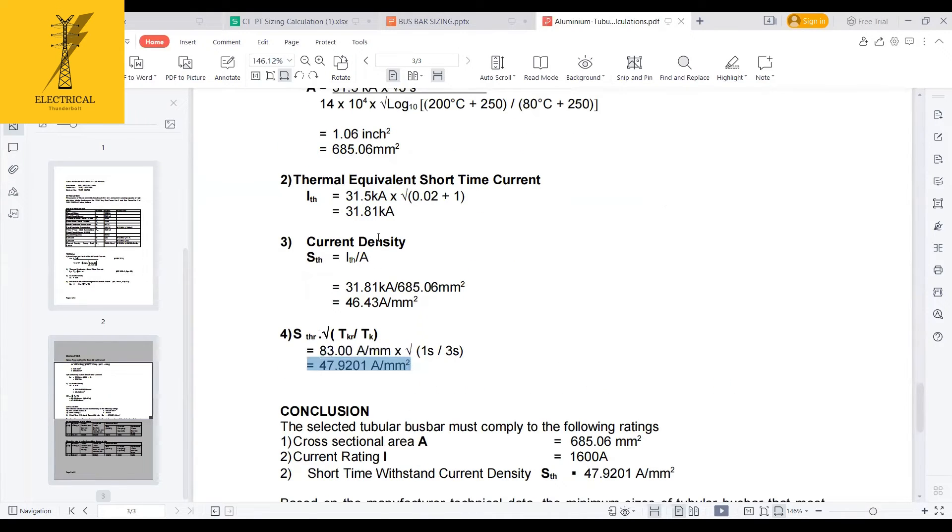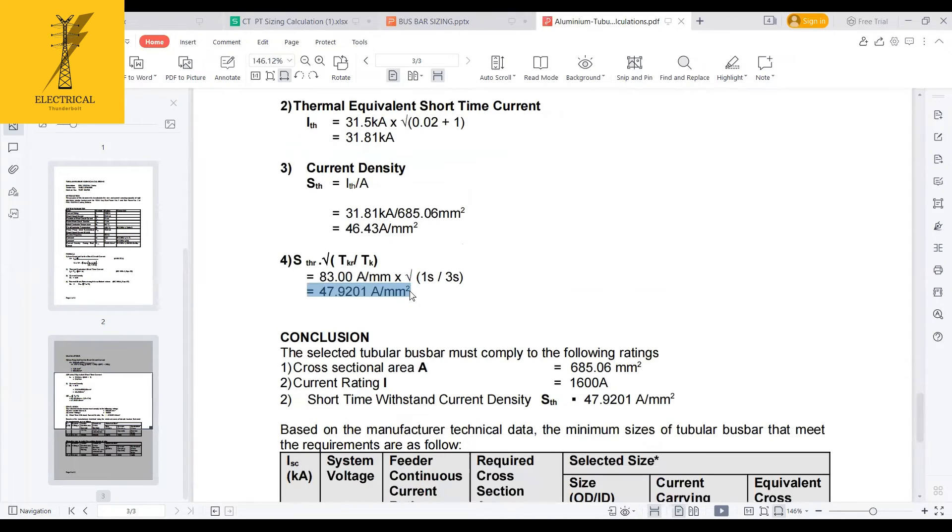But what is the current density during the short circuit? Which is 83 times 1 second by 3 seconds, which is 47. As my current density, when the fault occurred, at that time, this is the current density, which is less than my material one. Obviously, it is sufficient.